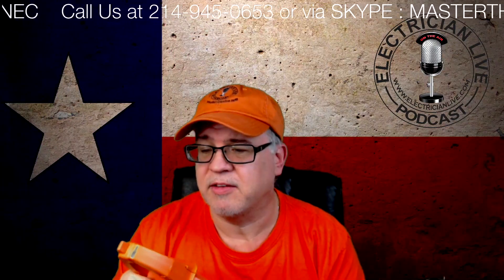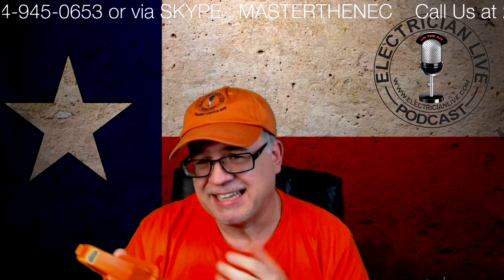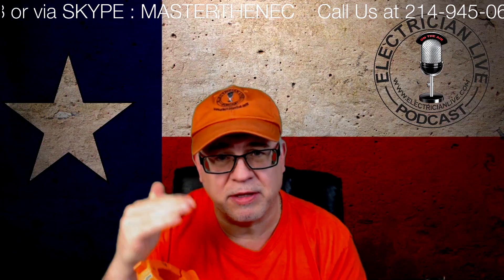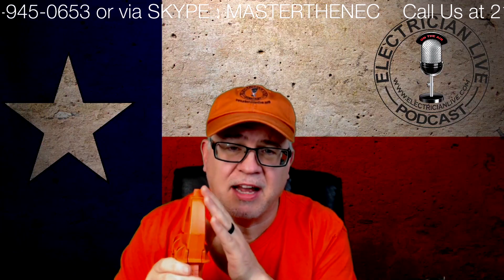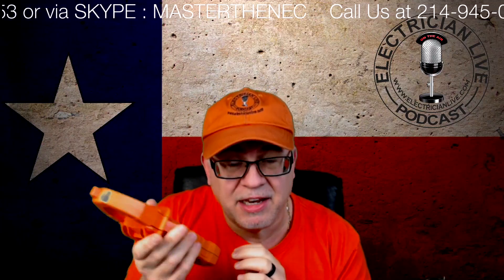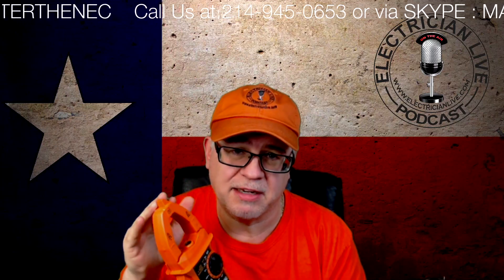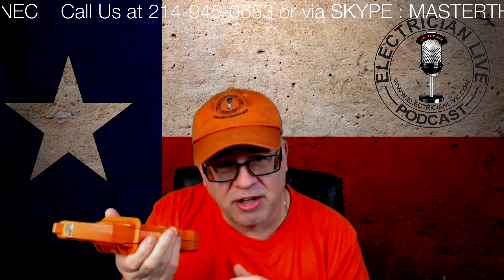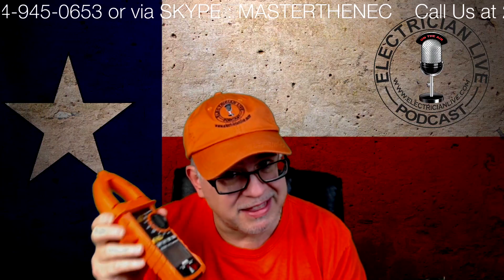It's got all its listings on it. It is CAT 3 for 1,000 volts, maximum of 1,000 amps with this unit. I like the inrush feature when I'm testing motors to see what the actual inrush is, and of course it has a hold feature. I was so impressed with it that I bought my brother one and gave it to him for a Christmas present. I love the fact that the non-contact is reliable — it's all in one. You've got your tick tracers, that's great, but I've got my meter and it is very reliable in how it activates. It's very sensitive, so I can literally trace it in the wall.